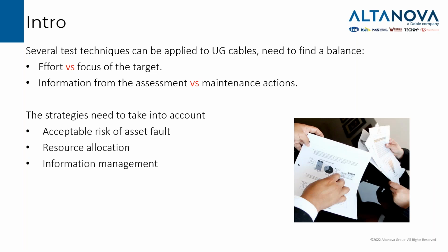We will see a lot of techniques that can be used on underground cable, but all of them have different characteristics, and we always need to find the balance between the effort of the test and the focus that we want to have on the target, as well as the balance between the information that we have from our assessment and the related maintenance action. So our strategy about the condition maintenance of the asset shall take into account the acceptable risk of fault for the specific asset, the resource allocation, and the information management from the eventual testing sessions or monitoring sessions.